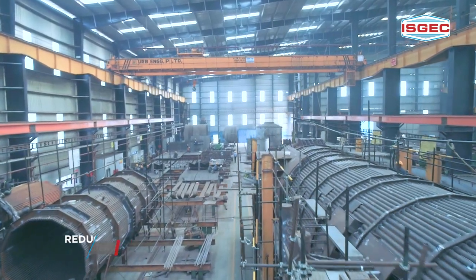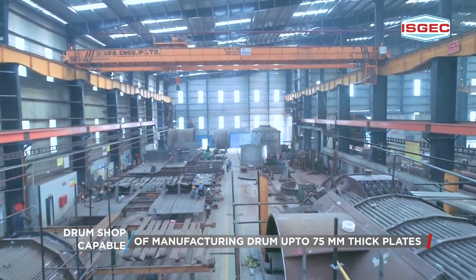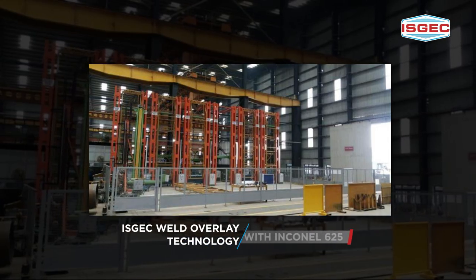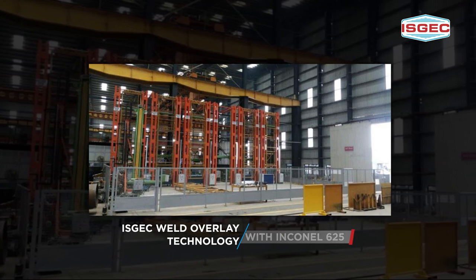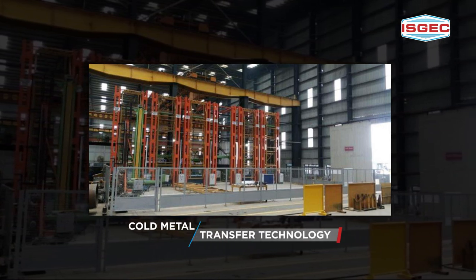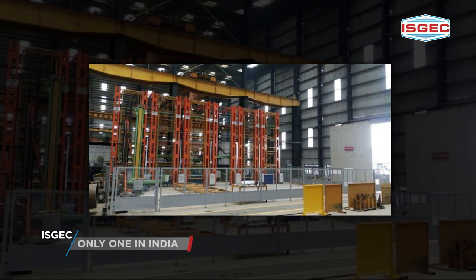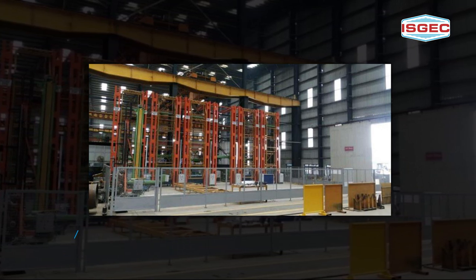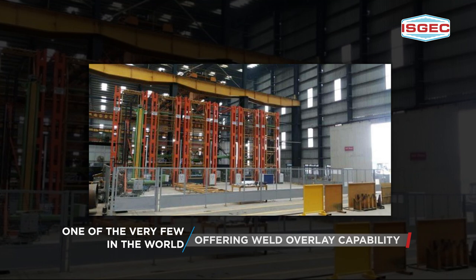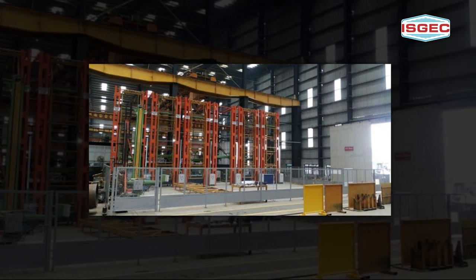This modularization concept reduces site work, erection time and optimizes shop fabrication leading to tangible quality benefits. At ISGEC we have also developed a special technology for weld overlay with Inconel 625, maintaining 2mm thickness of water walls and tube bundles through cold metal transfer technology. The process is done on machines sourced from Europe and makes ISGEC probably the only company in India and one of the very few in the world capable of doing so. With this technology we are able to accurately achieve the required chemistry and excellent weld quality in 2mm thick weld overlays.